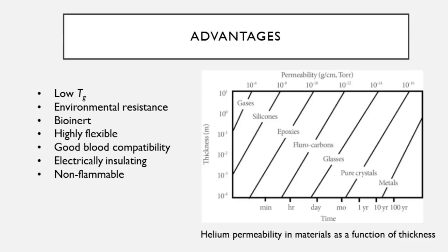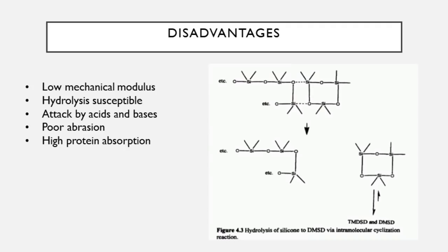Silicone's success in medical applications is due to several advantages. First, they have a low glass transition temperature, ensuring they remain in the rubbery, amorphous state at body temperature — also applicable in aerospace applications with large temperature swings, where silicones maintain ductility and flexibility. Silicones have great resistance to environmental factors, making them relatively bioinert in the body, and their low Tg makes them very flexible at body temperature. They also exhibit great blood compatibility — making them excellent for catheters — and are electrically insulating, hence their use in pacemakers. They are also non-flammable.